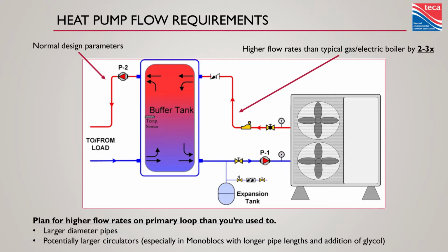For those that don't know what hydraulic separation is, it's a way of combining two separate circuits in a hydronic system so they don't influence flow within each other. So a change in flow on my load side does not represent any change in pressure drop on my source side, which means my flow rate stays consistent no matter what's happening on the load side. You can do this with closely spaced tees. You can do it with low loss headers. You can also do it with 4-port buffer tanks.